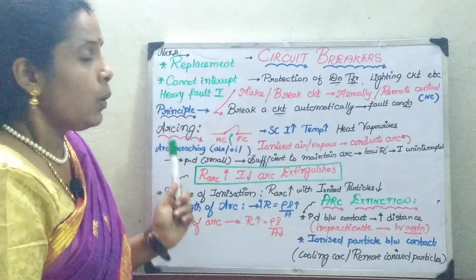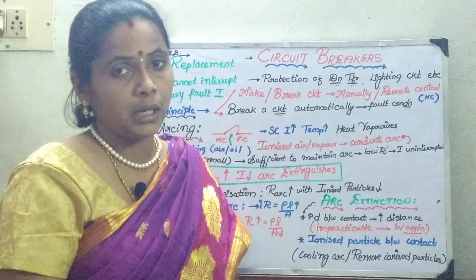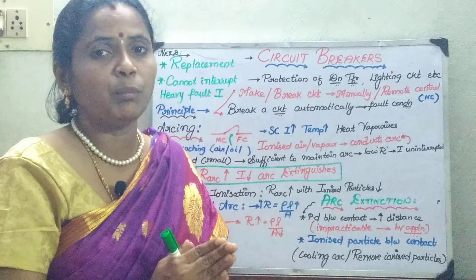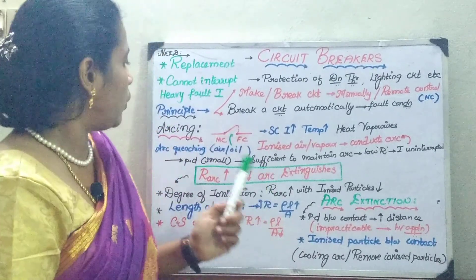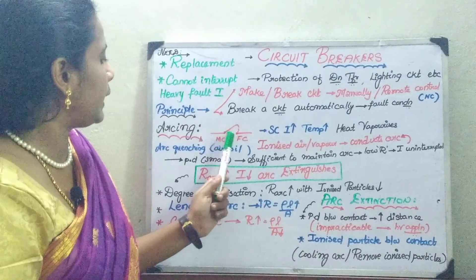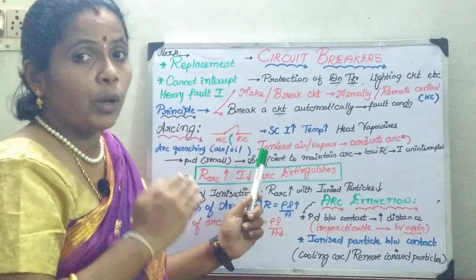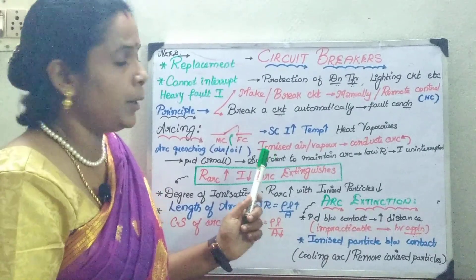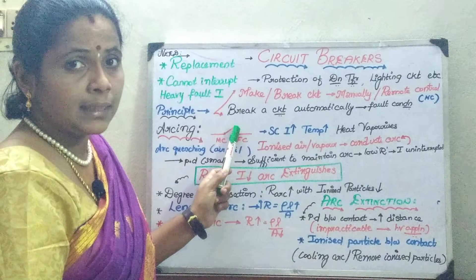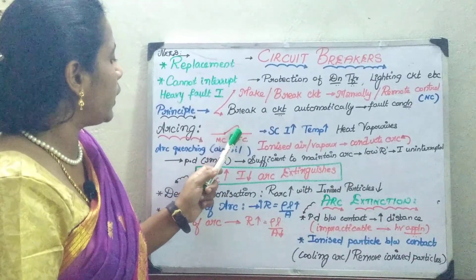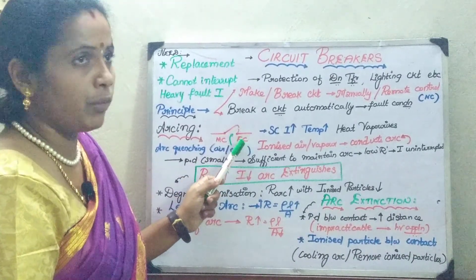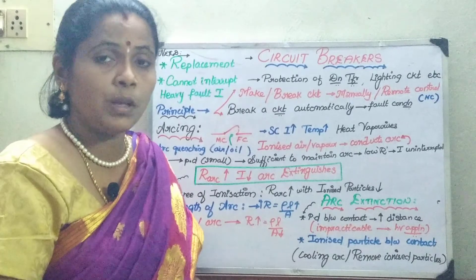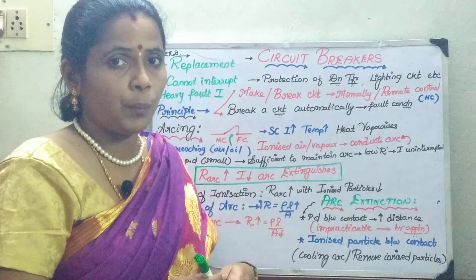Now we will see the operation of a circuit breaker. In a circuit breaker, one of the main problems is the arcing between the contacts. As we all know, a circuit breaker has two contacts: a moving contact and a fixed contact. Whenever a fault or short circuit occurs, a heavy fault current passes through. In order to interrupt it, the moving contact moves apart from the fixed contact, and the arcing medium flows through to quench the arc as soon as possible, protecting the power system components against damage.